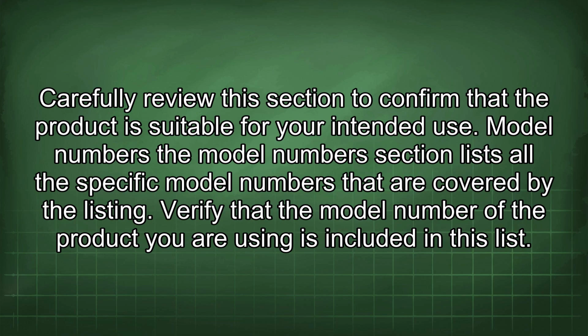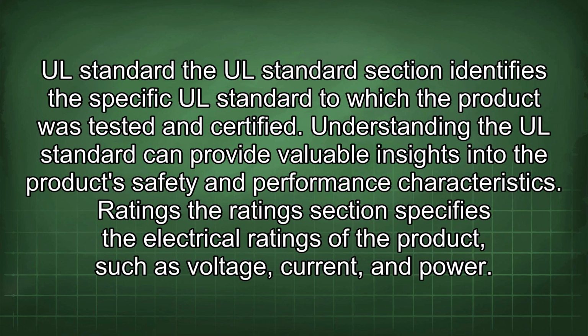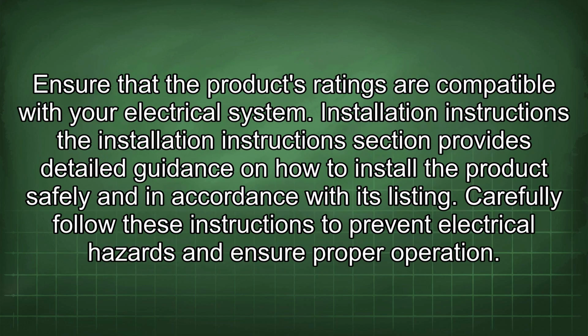Model numbers. The model numbers section lists all the specific model numbers that are covered by the listing. Verify that the model number of the product you are using is included in this list. UL standard. The UL standard section identifies the specific UL standard to which the product was tested and certified. Understanding the UL standard can provide valuable insights into the product's safety and performance characteristics. Ratings. The ratings section specifies the electrical ratings of the product, such as voltage, current, and power. Ensure that the product's ratings are compatible with your electrical system.